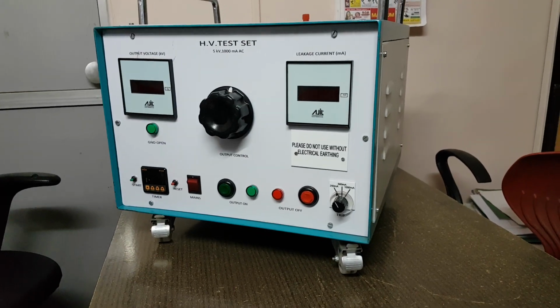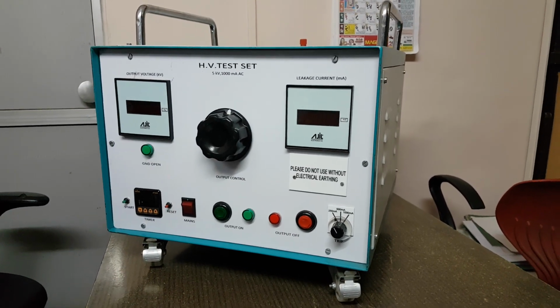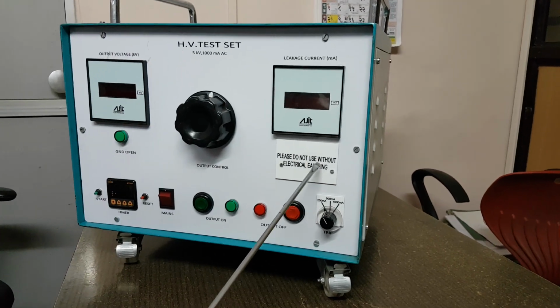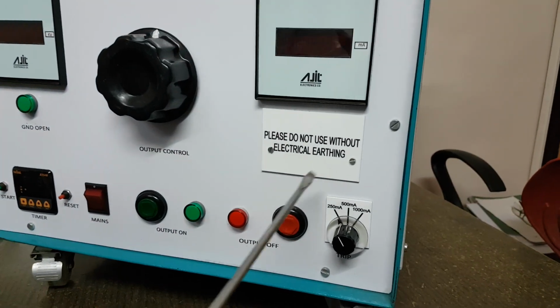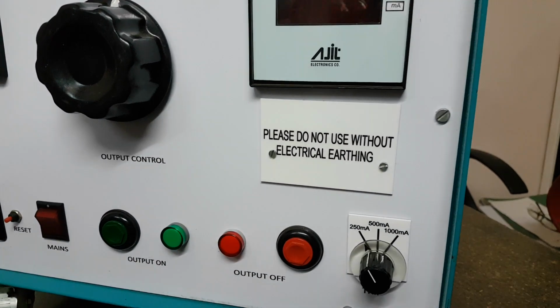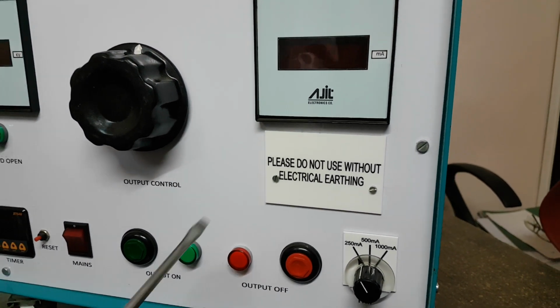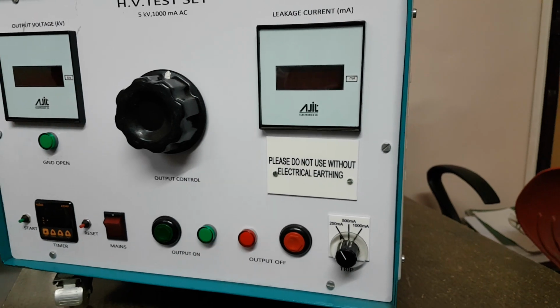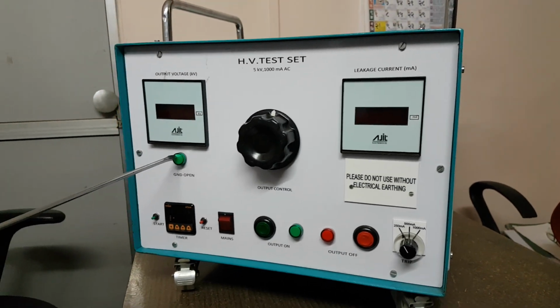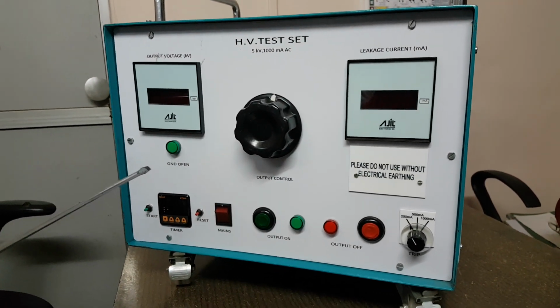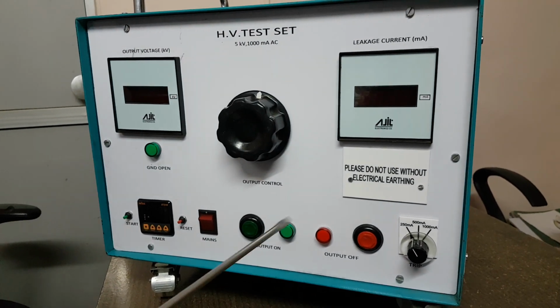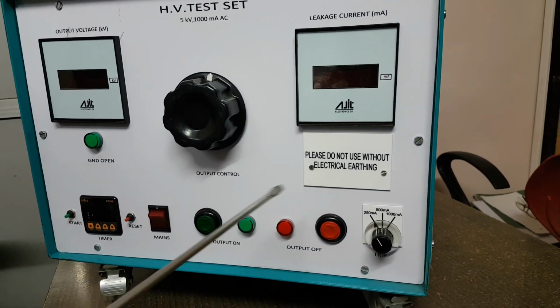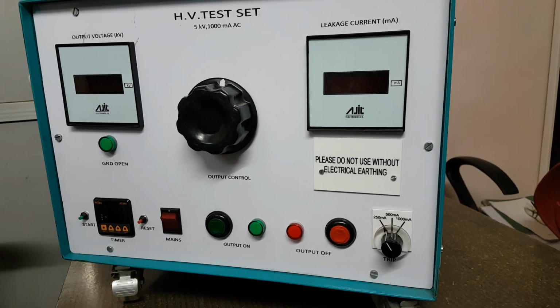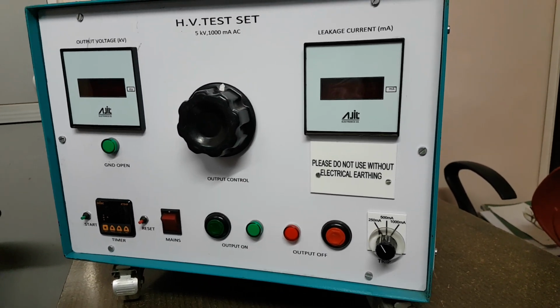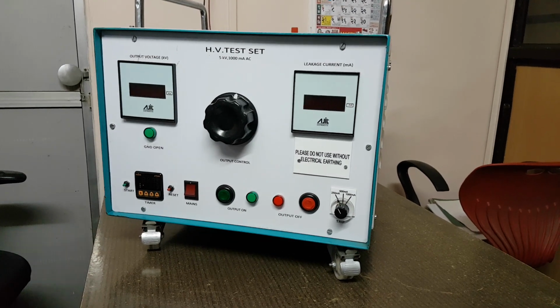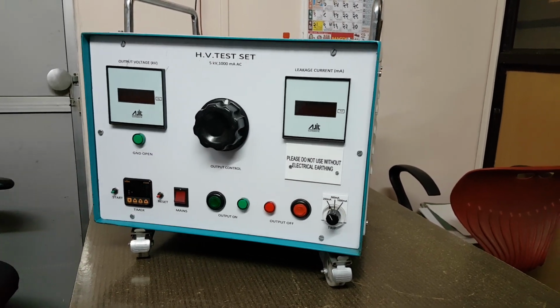Before putting on the instrument, two things are to be noted. One is, please do not use without electrical earthing. One instruction is mentioned on the panel of the instrument. This is very important. Even though we have provided an interlock for ground opening, or when the ground is not properly connected, still there is one instruction plate fitted here to make the user alert. Okay, now let us start operating.